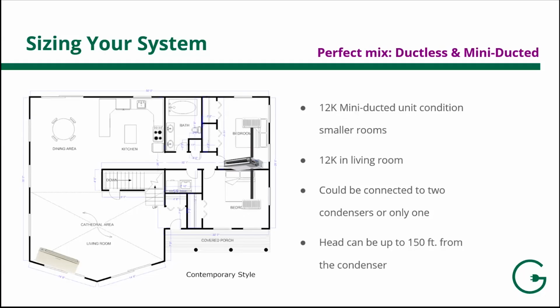These 2 can be connected to 2 separate condensers or 1 condenser. And generally, a condenser works most efficiently when it has fewer heads on it. You can put up to 4 or so heads per condenser. And heads can be up to 150 feet per condenser. Then to heat the main living area, you would have a 12K British thermal unit, as shown in this picture.